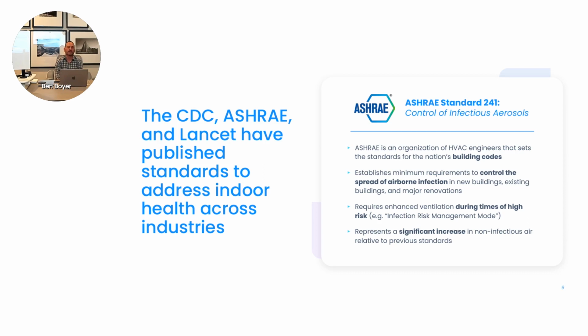241 took a different approach to looking at the problem. If you in essence only ventilate to the 62.1 standard, this minimum level, you are doing nothing to help prevent the spread of infectious disease within the built environment. I'll go through what the changes are, but they're monumental.